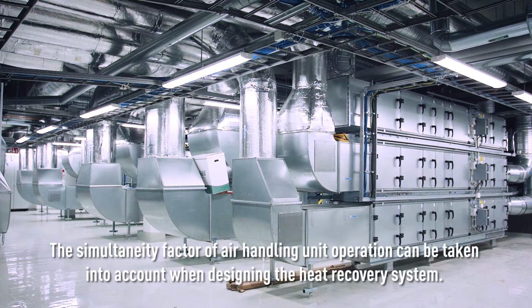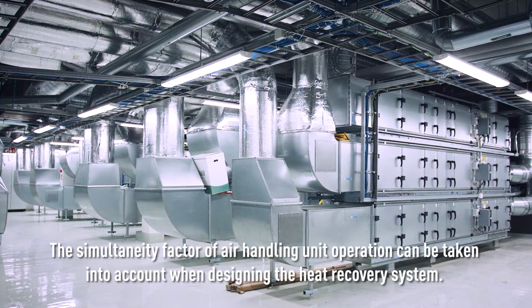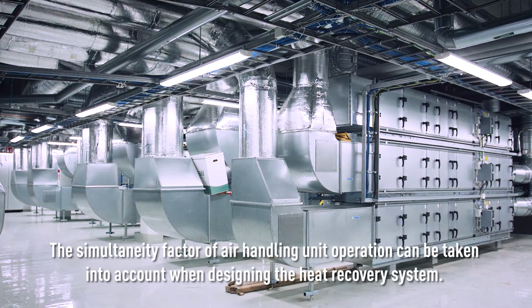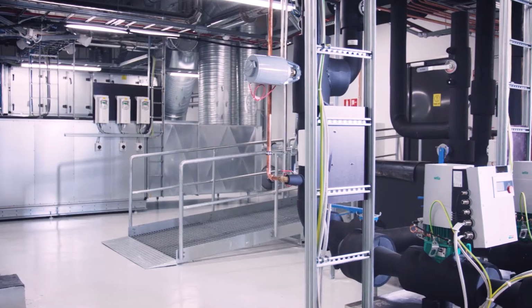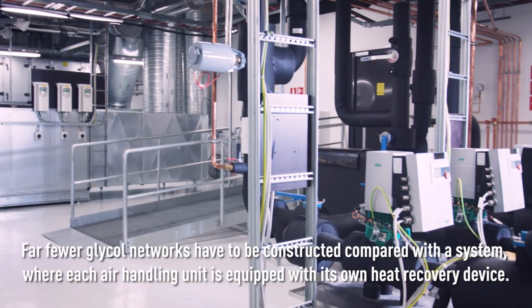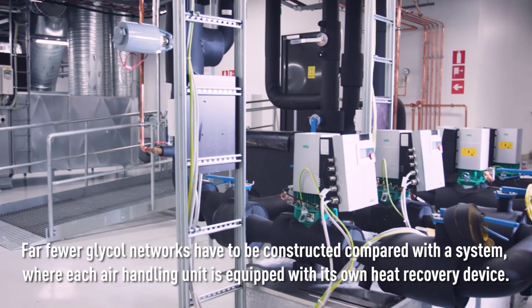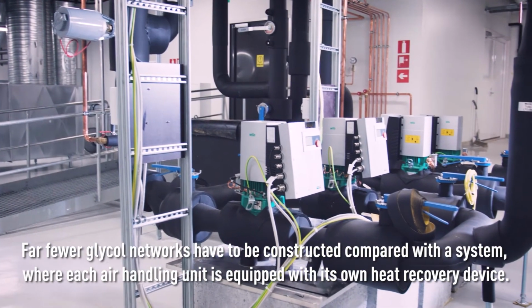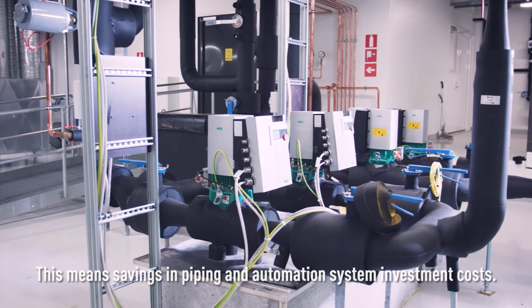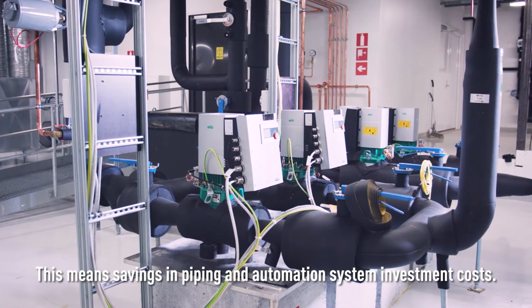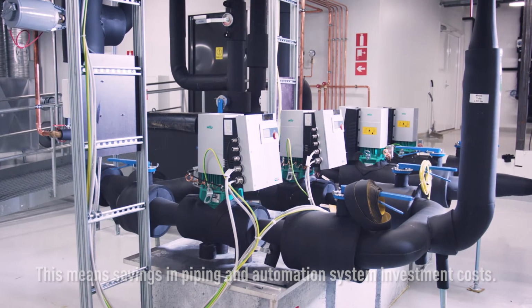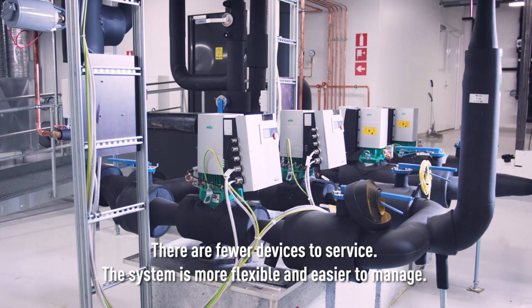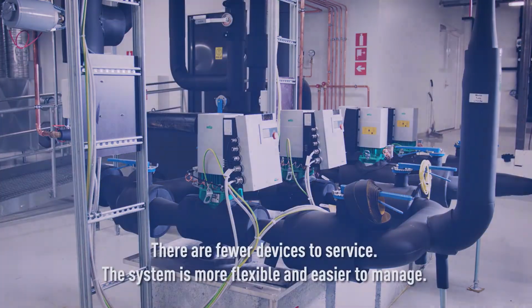The simultaneity factor of air handling unit operation can be taken into account when designing the heat recovery system. Far fewer glycol networks have to be constructed compared with a system where each air handling unit is equipped with its own heat recovery device. This means savings in piping and automation systems investment costs. There are fewer devices to service. This system is more flexible and easier to manage.